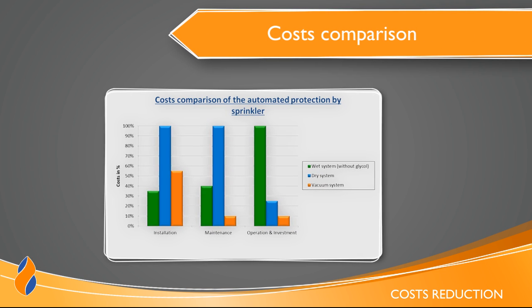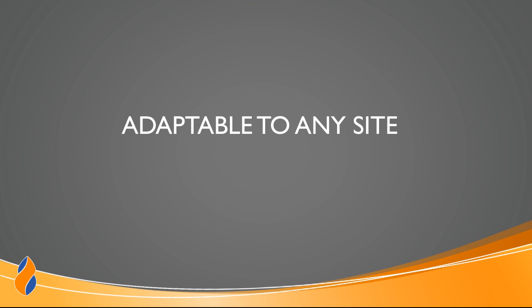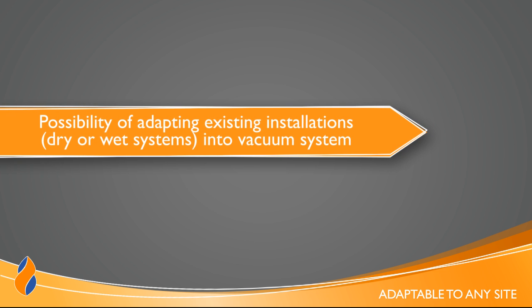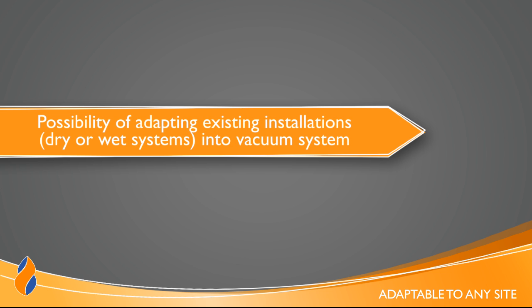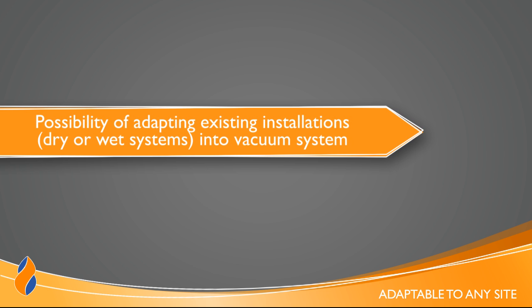When we compare the various fire protection sprinkler systems, the VACTEC vacuum system is the most profitable system in the medium and long term. Indeed, its maintenance, operation and investment costs are significantly reduced. The new VACTEC fire protection vacuum system can adapt to any type of building in any location. The VACTEC system offers the possibility of adapting existing dry or wet installations that are equipped with sprinklers.